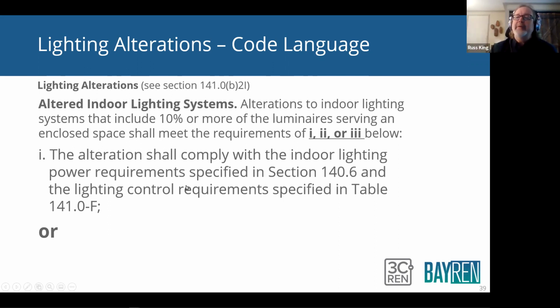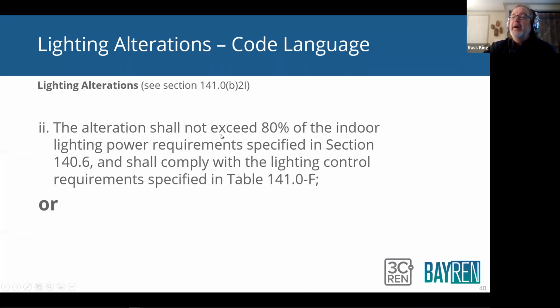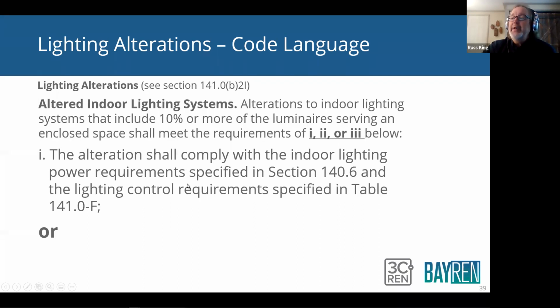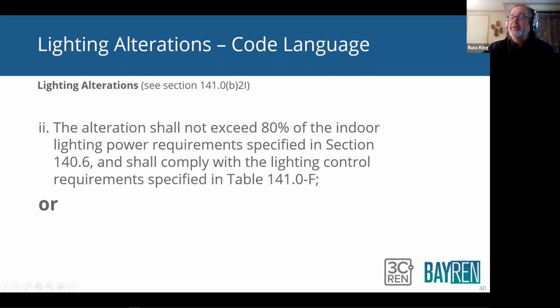So one is basically meet the lighting power density, all right? And this table is where it's going to list those controls. Okay. Number two, do not exceed 80% of the lighting power density. In other words, beat it by 20%. It's just another way to say beating it by 20% is to be 80% of that number or less in section 140.6, and then follow that table. And what you'll notice in this table is there's a different column. For just meeting your lighting power density, there's one column. For beating it by 20%, there's another column, and I'll show you that in just a second.